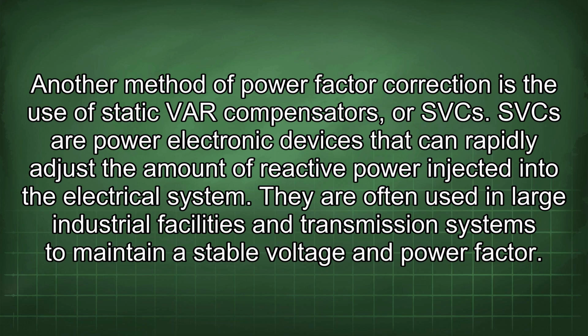Another method of power factor correction is the use of static VAR compensators, or SVCs. SVCs are power electronic devices that can rapidly adjust the amount of reactive power injected into the electrical system. They are often used in large industrial facilities and transmission systems to maintain a stable voltage and power factor.